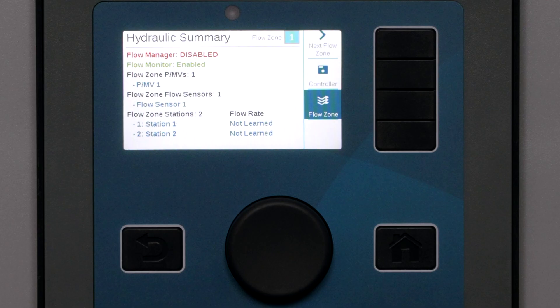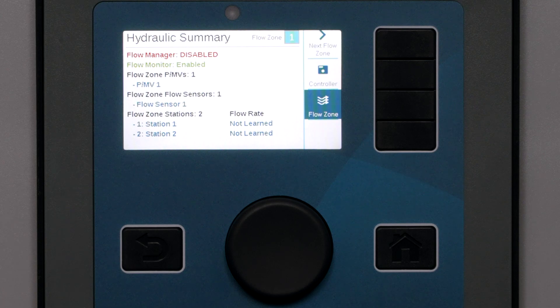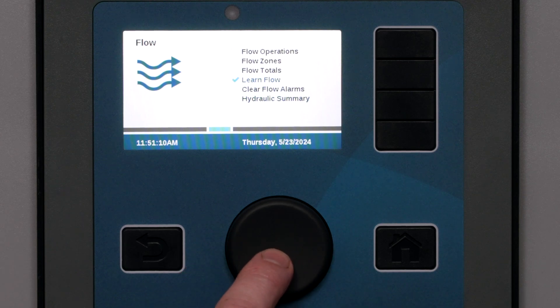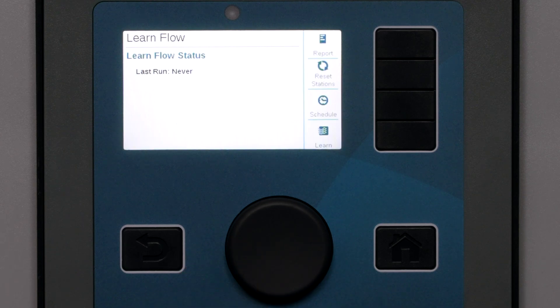When all the stations in the flow zone are attached, you are almost done. Now the key step is to learn the typical flow by station. It's important to know that the controller will only attempt to learn flow for stations that have runtime — these are assigned on the programs menu. Go to the Flow menu and select Learn Flow. This will show the last time flow was learned at the controller, and on a new setup it will say never. You can begin the flow learning process immediately — this can take up to five minutes per station, but is usually quicker.